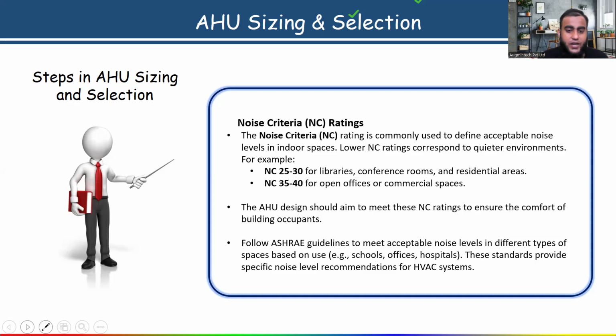So the standard provides specific noise level recommendations for HVAC systems. Okay, in which room, how much for commercial. So generally, here I have given you the idea. If you are designing for residential or this type of space, go for this one range. If it is an office or commercial space, it is better to maintain a maximum noise criteria of 40 decibel. Don't go beyond that. If it is a shopping mall, up to 45 decibel you can go, no problem. Okay, clear this thing, tell me please.